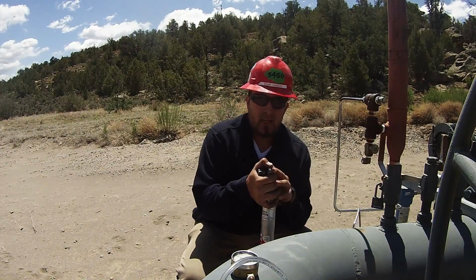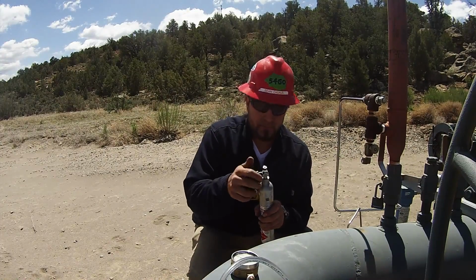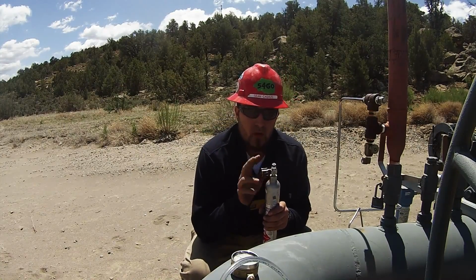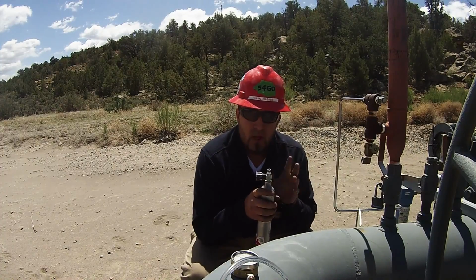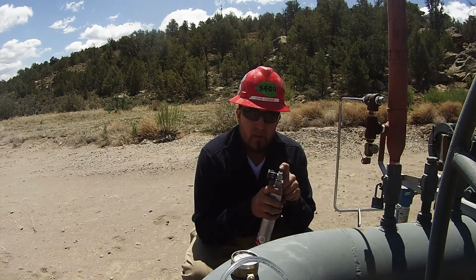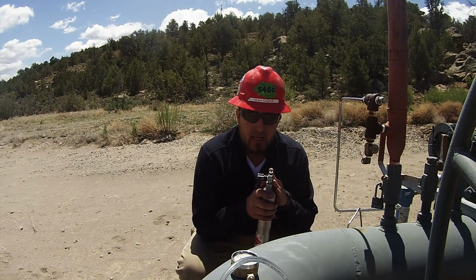I can feel it pressing against my finger. We have a bad seat in this one. If this ever happens to you, you have two options. If you have a spare bottle that you can retake this sample with, go ahead and throw it in the spare bottle. Let us know which valve is bad on this bottle. Or if you don't have a spare bottle, go ahead and thread tape it.